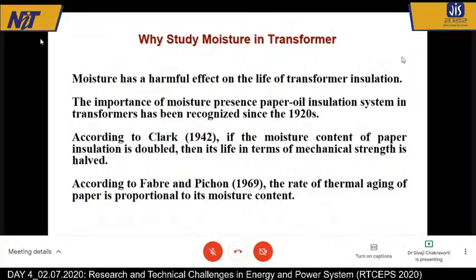But after that, I will talk about how the paper deteriorates. One of the most important aspects that was found in the 1920s is that moisture is the most detrimental part of the insulation, particularly paper insulation. By the way, let me tell you, if oil gets deteriorated in any way, we can change the oil. But if paper gets deteriorated, we have to change the entire winding, which means it is 50% of the transformer cost. So people are less bothered about oil. People are bothered about paper.